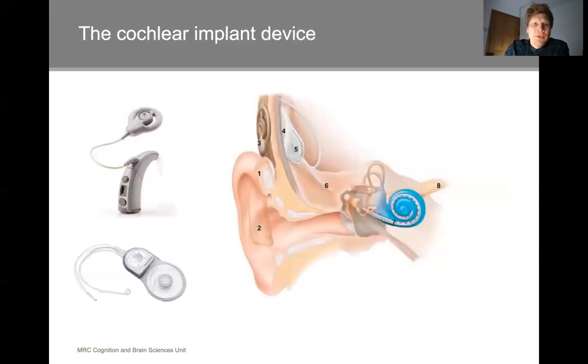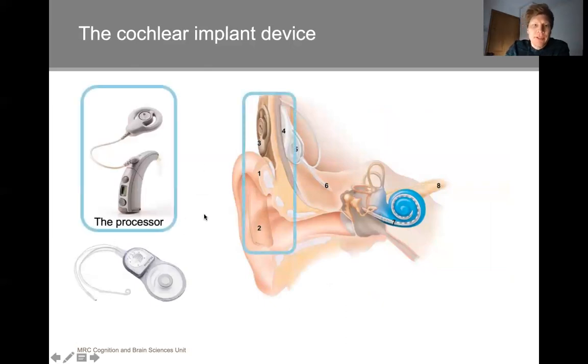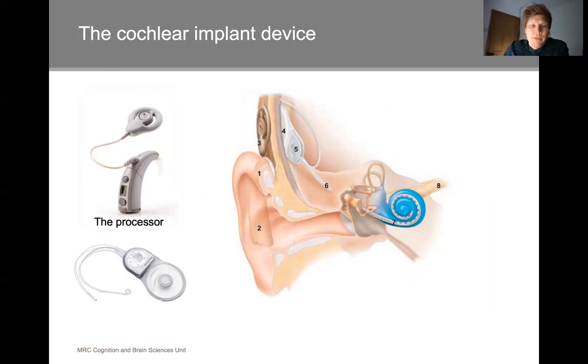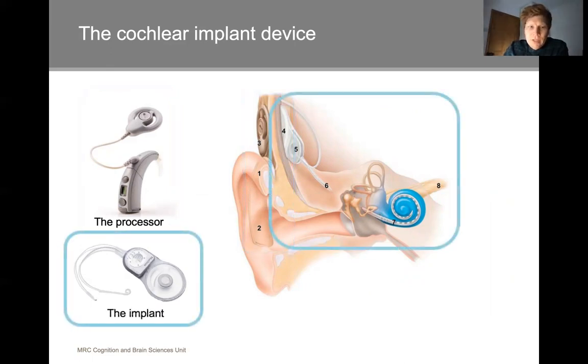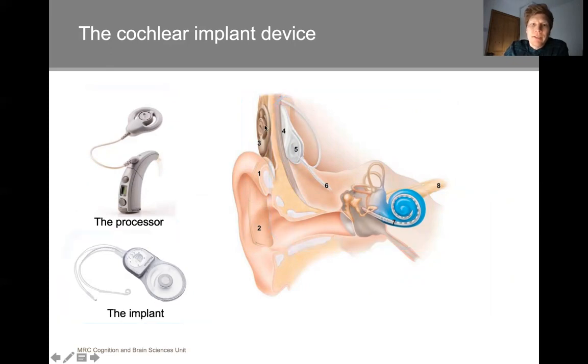So how does it work? The cochlear implant consists of two parts. We have an outer part, the speech processor, which looks a bit like a hearing aid. It's worn behind the ear or on the head. And we have the internal part, the implant. These two hold together via a magnetic link, and they have a transmitter coil here and a receiver coil, and they hold here, they talk to each other via magnetic fields.